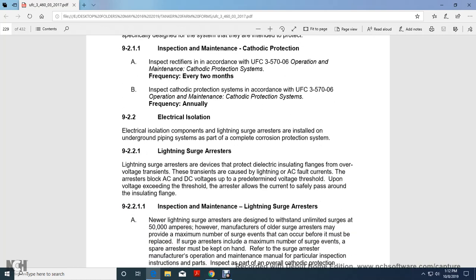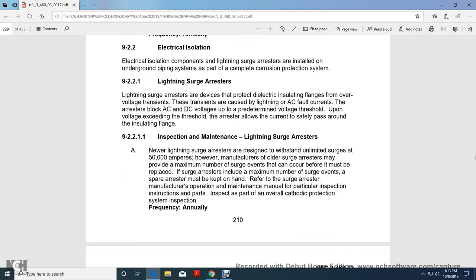9.2.2, Electrical isolation. Electrical isolation components, including lightning surge arresters, are installed with the underground piping system as part of the overall corrosion protection system. Lightning surge arresters are devices that protect dielectric insulation flanges from overvoltage transients caused by lightning or AC fault currents. The arresters block AC and DC voltage up to a predetermined voltage threshold. Upon the voltage exceeding the threshold, the arrester will allow the current to safely pass around the isolation flange.